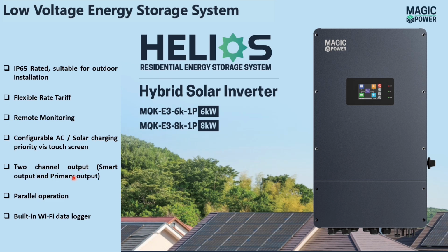Basically, the smart output is for those loads which we want to be disconnected at a certain battery percentage. For example, we choose 60% for this load disconnection. So at 60% this kind of load will be disconnected, but the primary output or the primary load will be connected all the time and will be fed by the energy storage system.